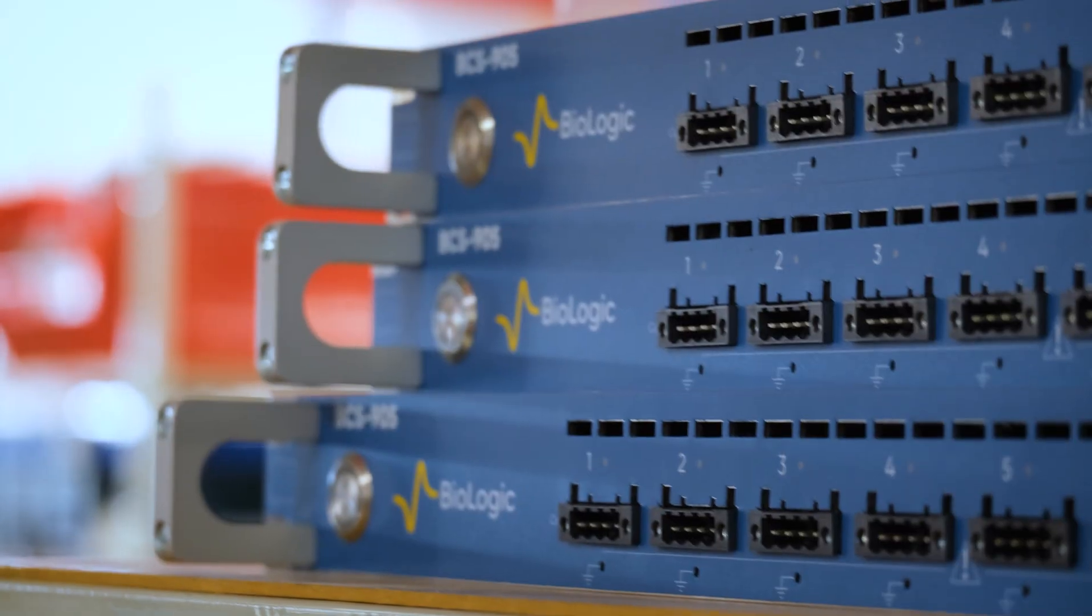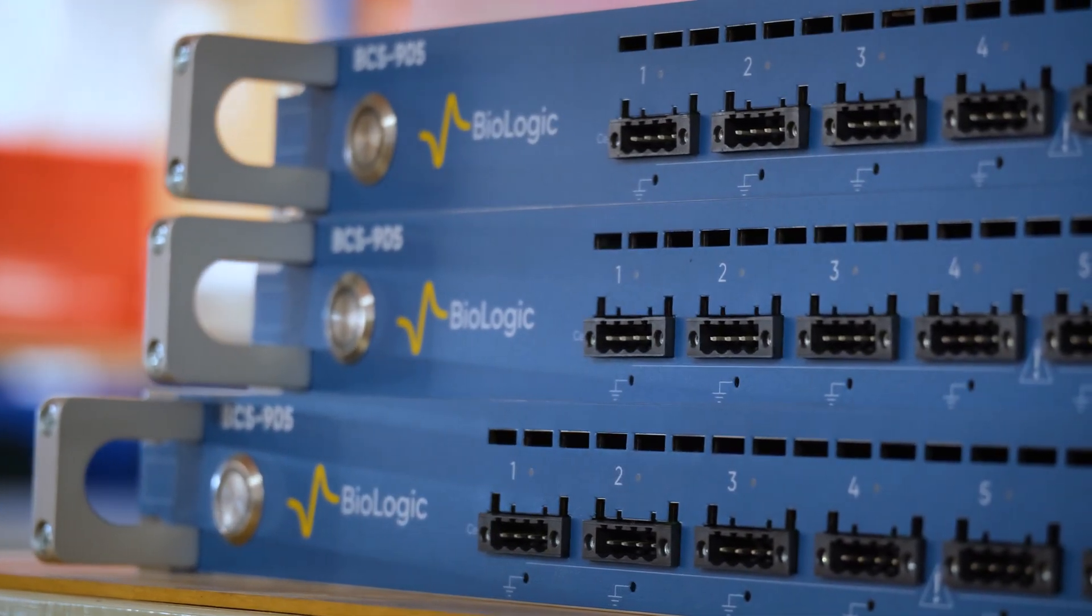At BioLogic we have several models able to adapt to various current level requirements for various battery capacities and C rates. The quality of the battery cycler is not the only important thing—how you connect the battery to the instrument also matters. That's why we have these four-point battery holders which are able to make a simple and precise connection.